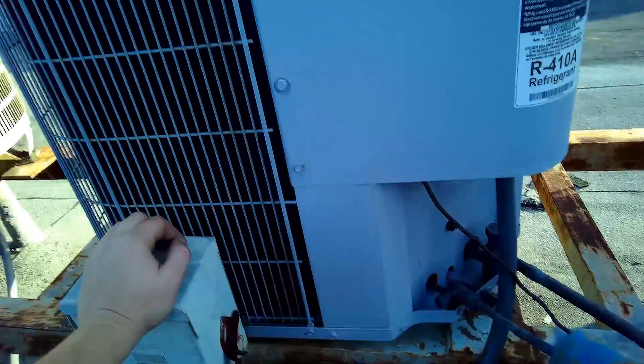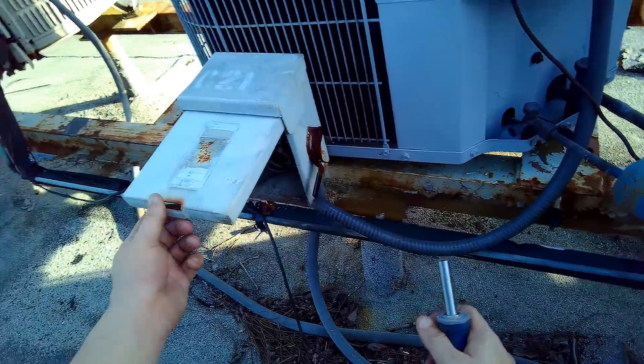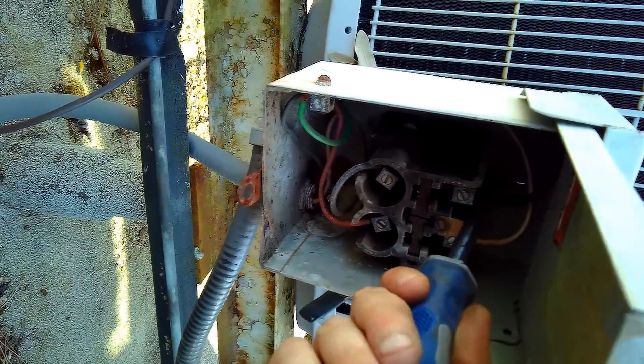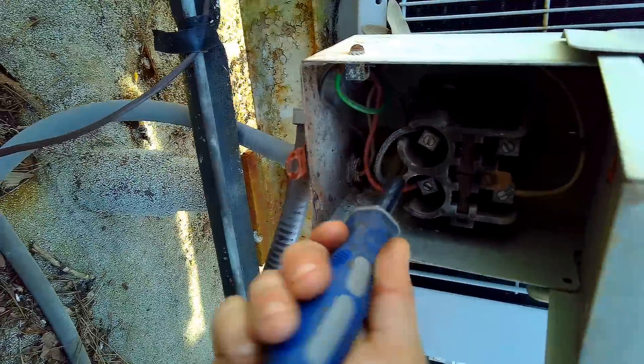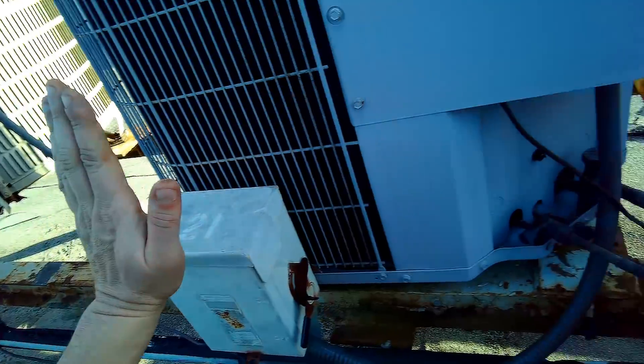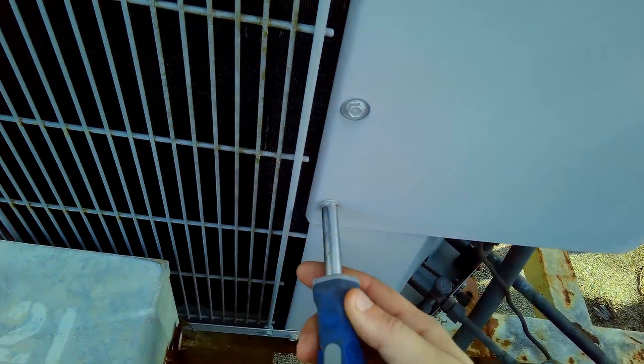Now, turning the power off to the unit probably doesn't do anything if sometimes these wires up here are bypassed down here — that means somebody has bypassed this disconnect. But in our case, they have not bypassed the disconnect.